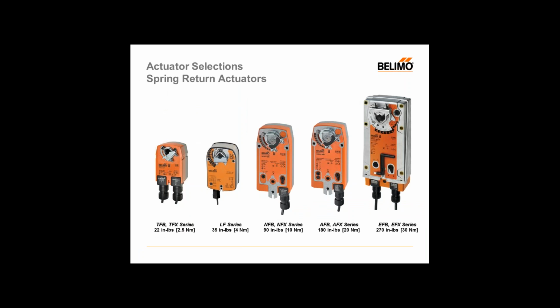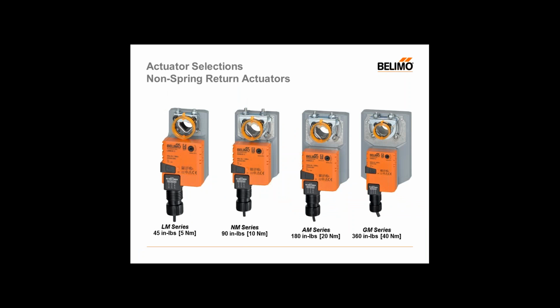Now, knowing this information, we move on to actuator selection. So now we've narrowed it down, what do we need? Well, if you're familiar with the Belimo actuator offering, you know we have a spring return actuator line, starting with the TF series, which is the smallest at 22 inch-pounds, all the way up to the EF series at 270 inch-pounds. Or a non-spring return line also, starting from the LM series at 45 inch-pounds all the way up to the GM series at 360.